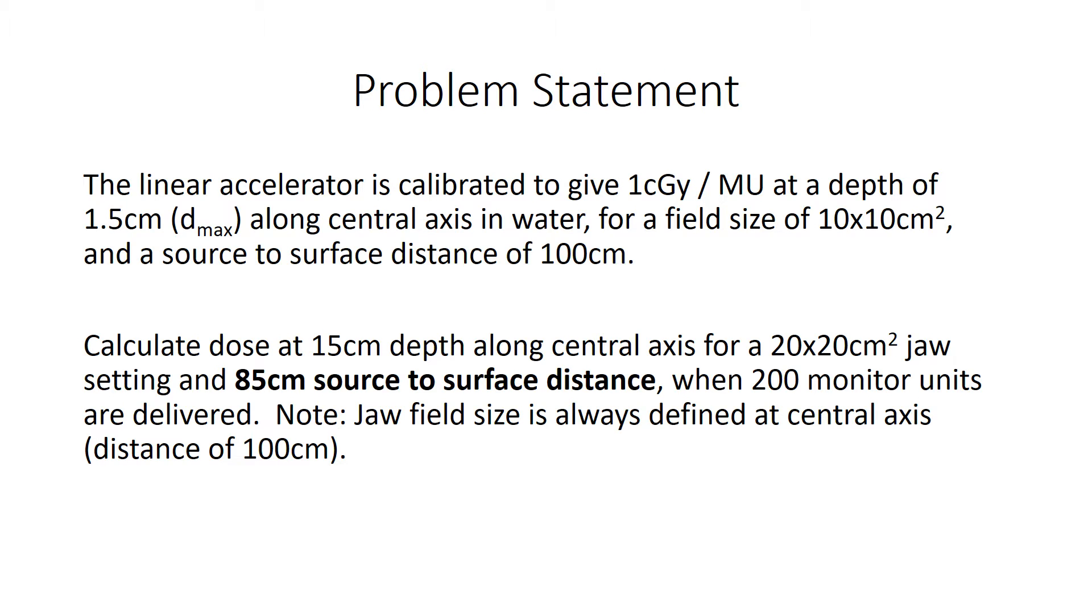First, we know that the LINAC is calibrated to give 1 centiGray per monitor unit at D max with a source-to-surface distance of 100 cm. We're now going to calculate dose at 15 cm depth along central axis for a 20 by 20 field size and an 85 cm source-to-surface distance and delivering 200 monitor units.